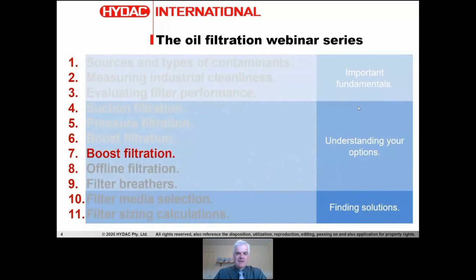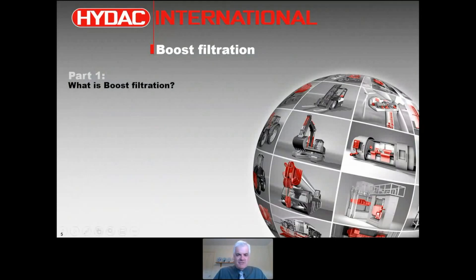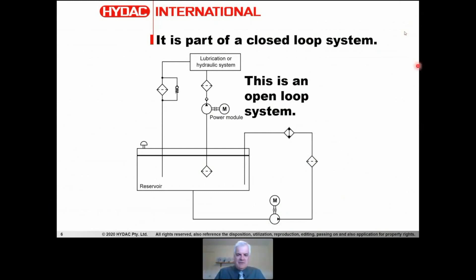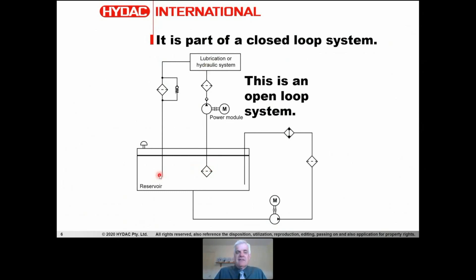What is boost filtration? Boost filtration is part of a closed loop system. The systems we've been talking about in previous webinars have all been open loop. In an open loop system you draw oil from a reservoir, send it via a pump through a filter into your system, back through another filter, and back to the tank — there's a disconnect between outlet and inlet.